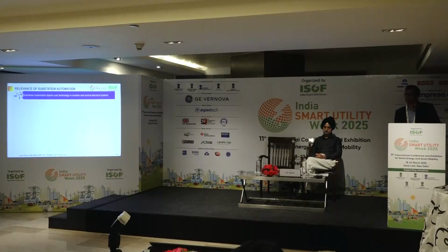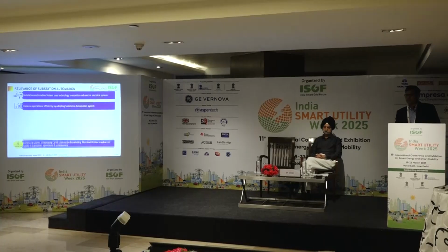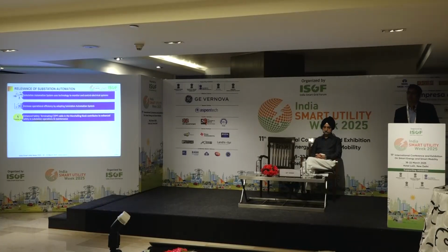Relevantly, substation automation system uses technology to monitor and control electrical systems. It increases operational efficiency as the substation system has evolved to the digital substation, where we can have enhanced safety because CT and PT are connected in the switched marshalling kiosk, so operation engineers, operation personnel, and maintenance personnel safety is enhanced. It also reduces environmental footprint by using digital substation - less copper cable, fewer panels - we can reduce the size of the substation control room, which contributes to less carbon footprint.